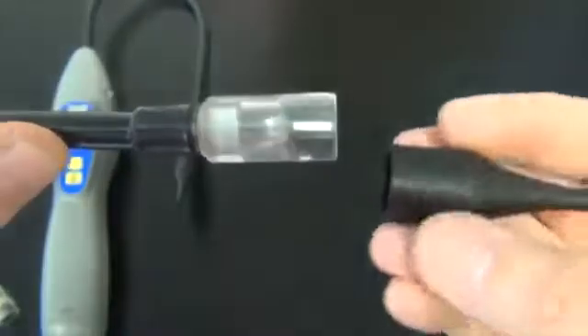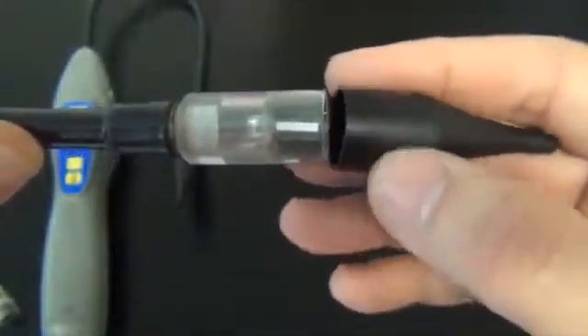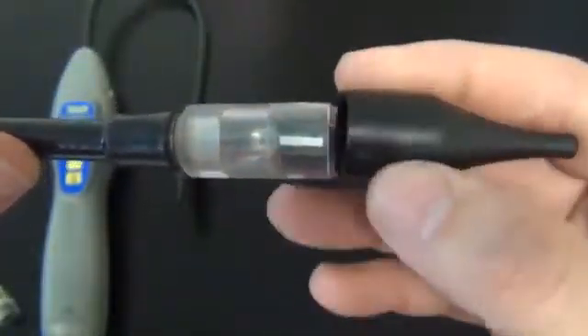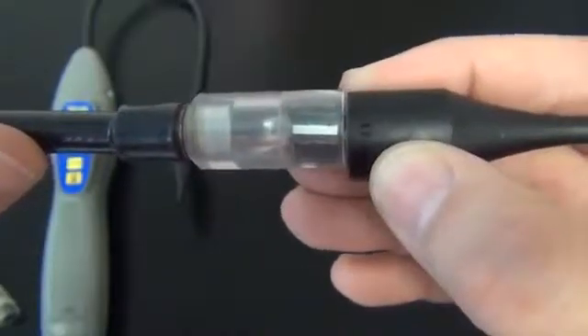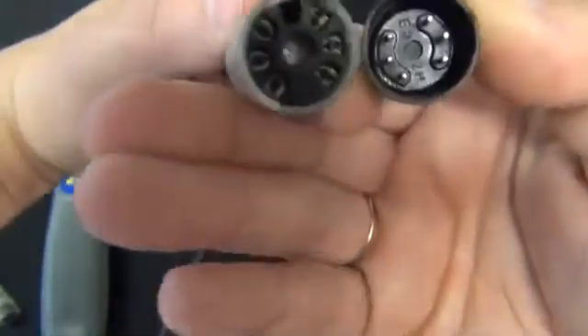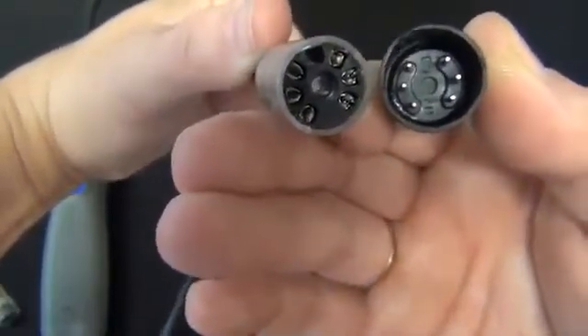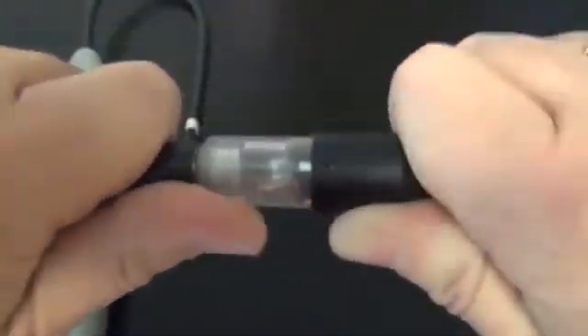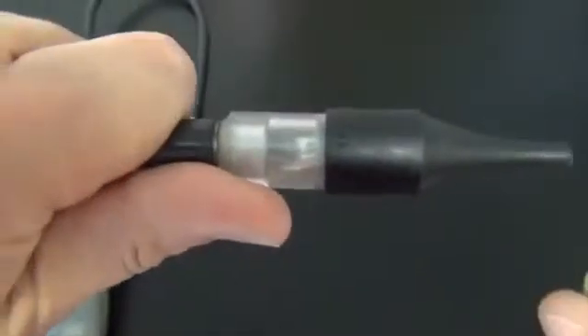On sensor type A, you need to make sure that you find the dimple which lines up with the line. If you look, the pin sockets and pins should be in the same orientation. You will line the dimple up and make sure it is pushed on completely.